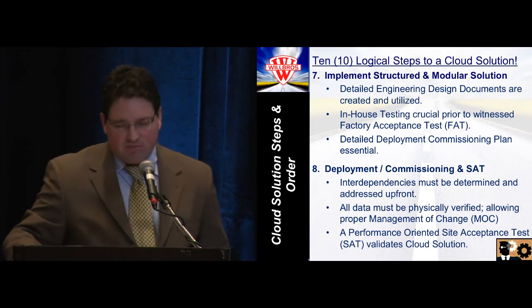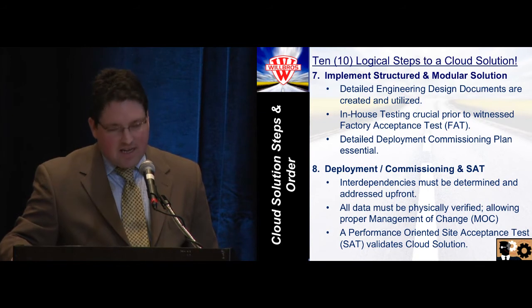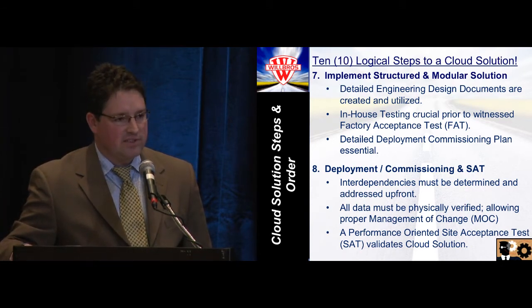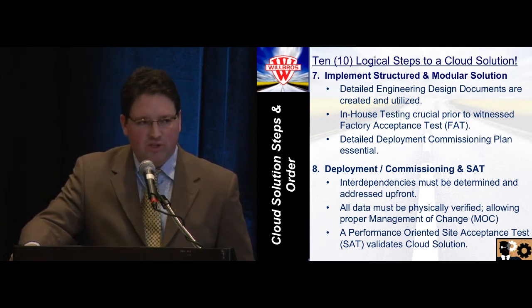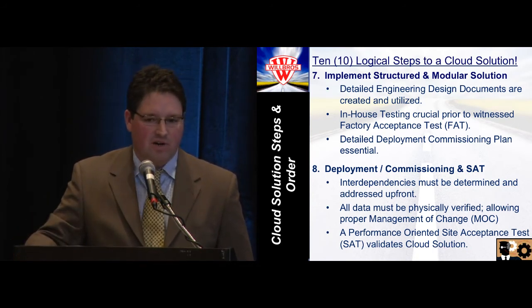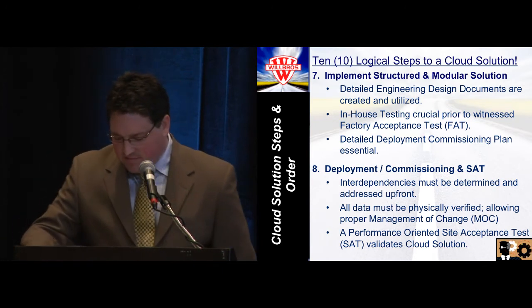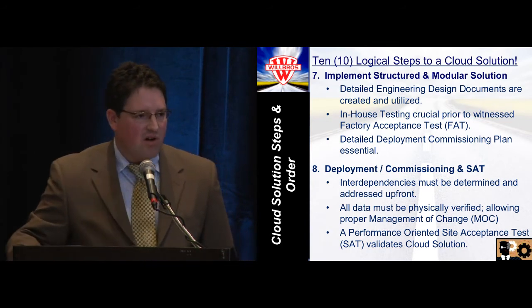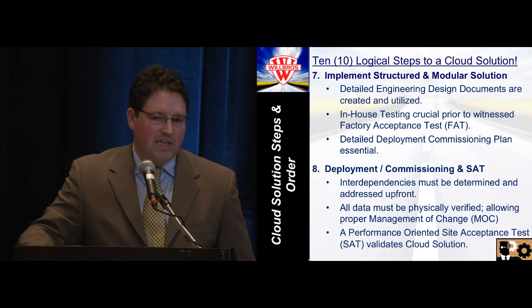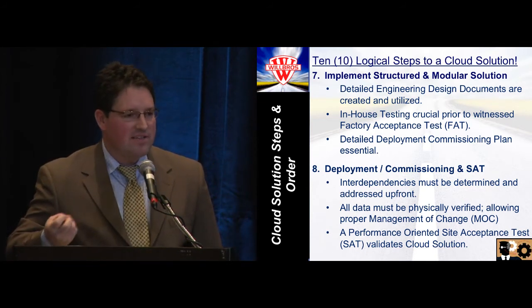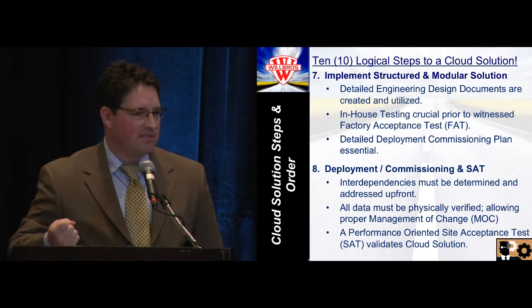Step six is to revisit performance validation goals — the pilot test dictates this. Be flexible with your goals because you will uncover physical limitations. Make your compromises against known and documented risks and issues. Step seven is implementing a structured modular solution approach. For critical infrastructure with a 50-year-old pipeline and many interdependencies, use a traditional engineering approach: detailed engineering design documents up front, in-house factory acceptance tests, and a detailed commissioning plan to minimize operational disruption. All data must be physically verified into your cloud solution, then implement a Management of Change (MOC) procedure to protect data integrity.